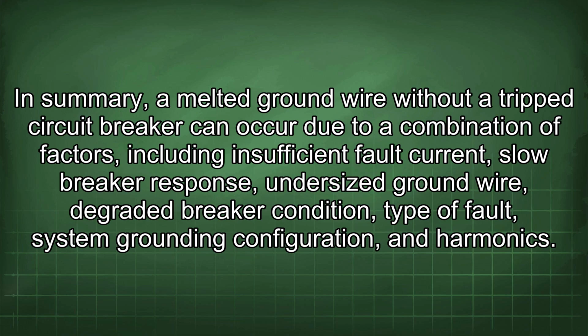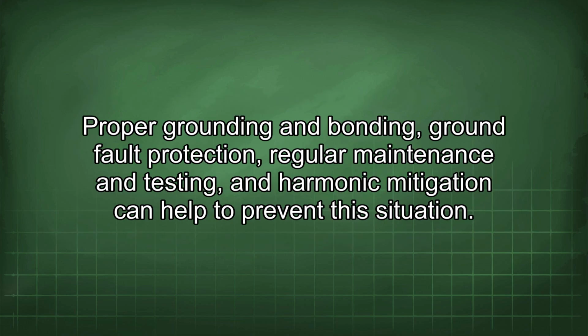factors, including insufficient fault current, slow breaker response, undersized ground wire, degraded breaker condition, type of fault, system grounding configuration, and harmonics. Proper grounding and bonding, ground fault protection, regular maintenance and testing, and harmonic mitigation can help to prevent this situation.